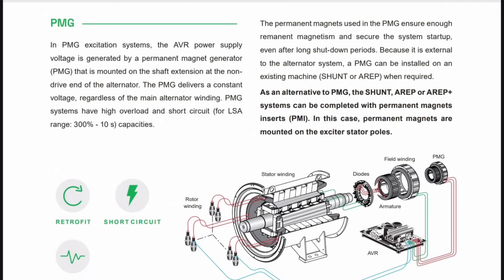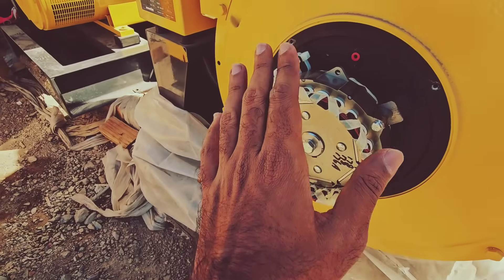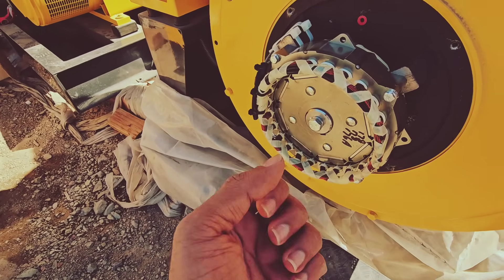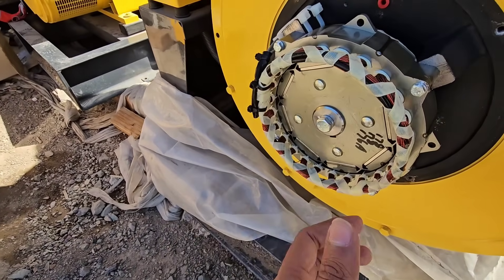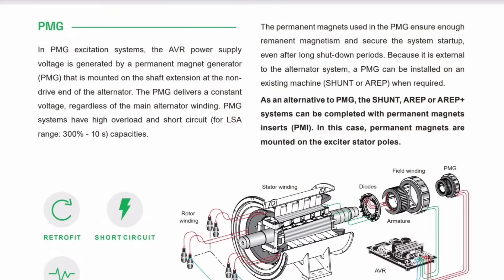The second type is the PMG excitation system, which is widely used in industrial generators. A small permanent magnet generator, PMG, is mounted on the same shaft as the alternator. This PMG produces a small AC voltage independently from the main alternator, which is sent directly to the AVR. The AVR converts this AC into DC and excites the rotor winding completely independent from the alternator's main voltage. PMG systems don't need residual magnetism to start and provide much better voltage stability during sudden load changes or short circuits. That's why PMG alternators are used in critical applications like hospitals, data centers, and industrial backup generators.